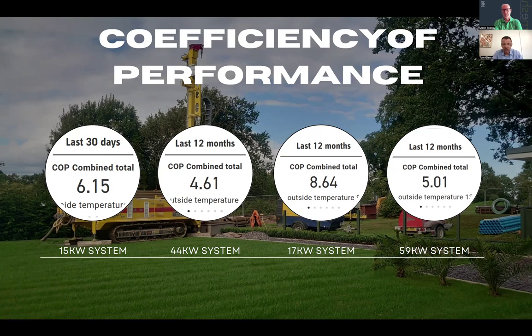Some of our systems you can see working at 8.6 COP, which is really good. The boreholes are really well saturated. The client is not heating all the time at the house, so his efficiency is really great. But normally you would say our efficiency would be around the 4.5 to 5 mark, and that would be a good system with good efficiency.